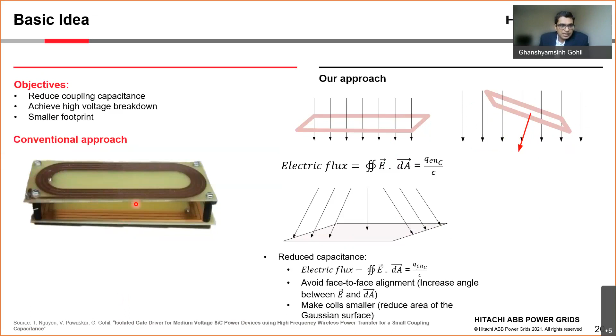Here is the realized prototype, where the power supply for the gate driver is almost hidden. The transmitter and receiver coils are embedded in separate PCBs - the transmitter coil is on one PCB, and the receiver coil is inside this box, potted in epoxy to achieve the required clearance and a smaller footprint.